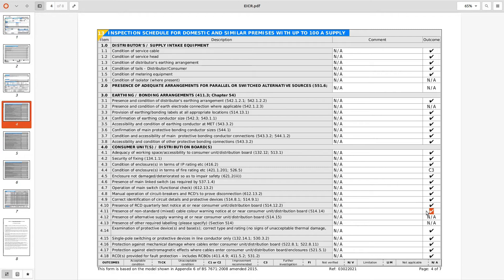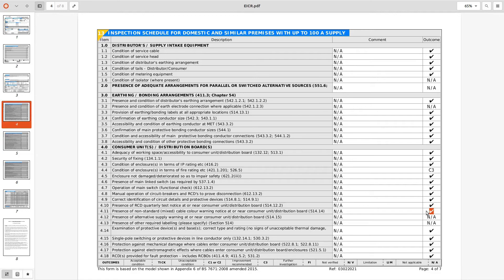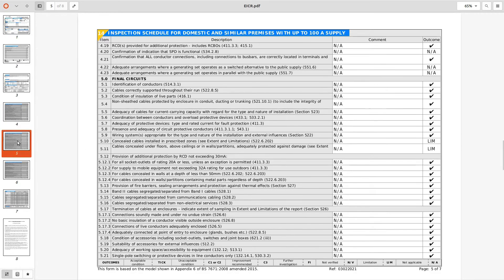Looking at the last one 418 RCD protection for fault protection was put a tick in there. We've got circuits one to six without any fault protection, oh I've got fault protection by means of the circuit breaker, but I don't know why it's ticked that to be honest. But let's look at the next page, next page 419.